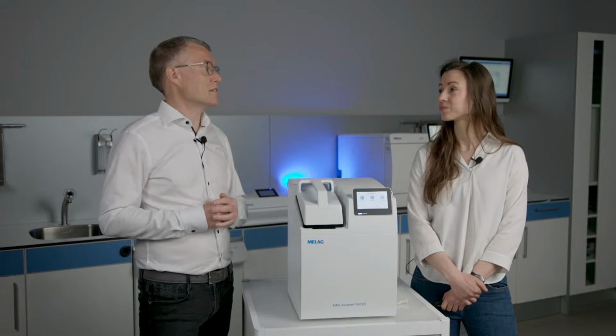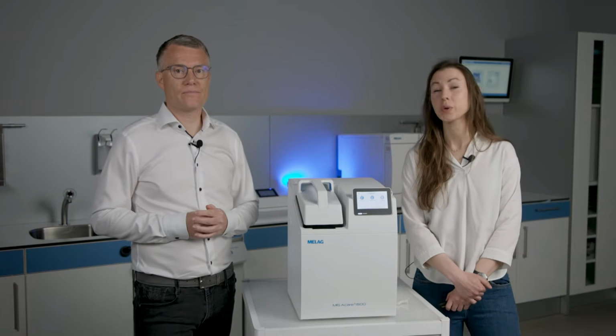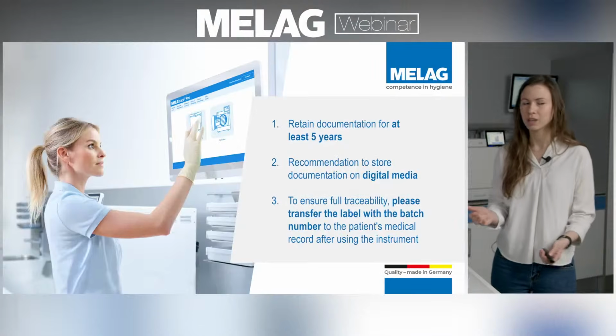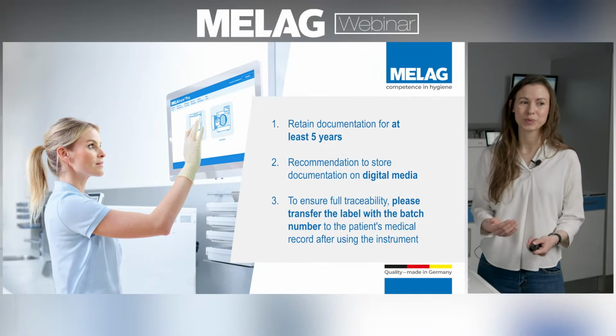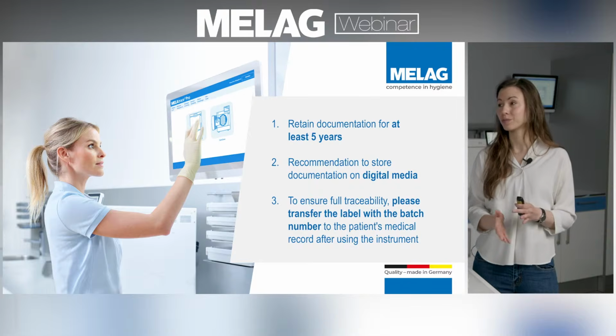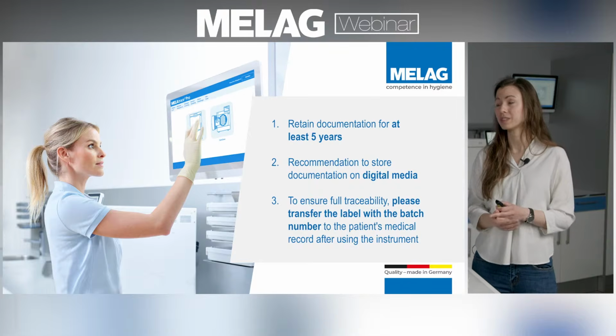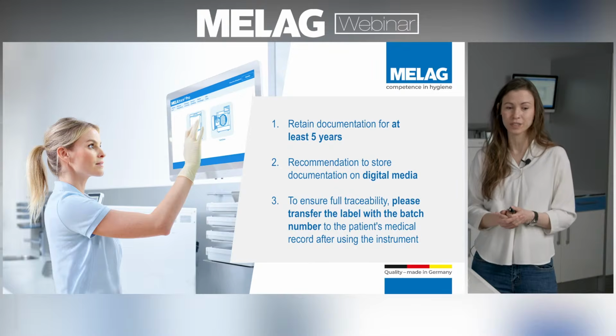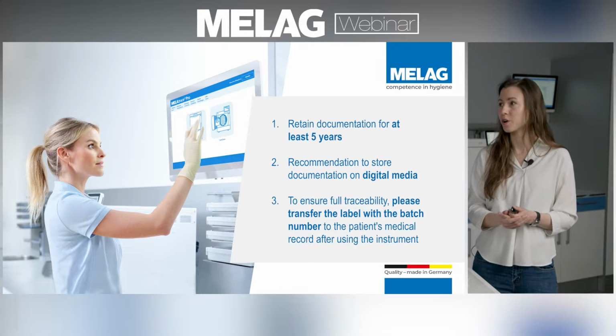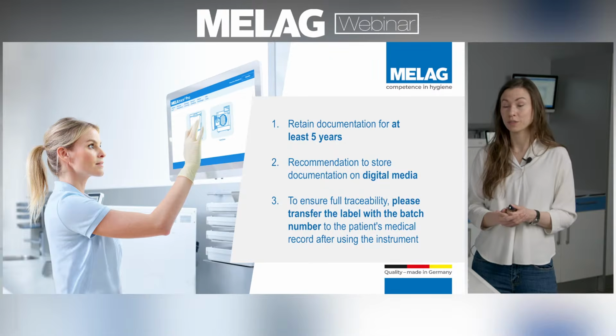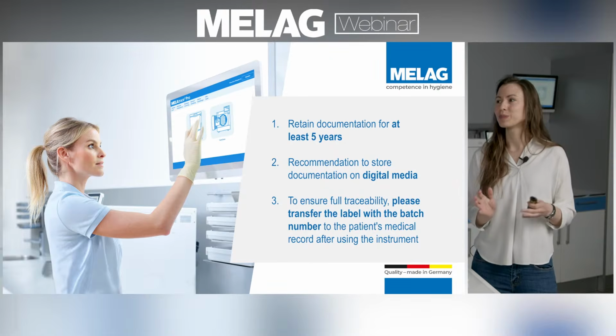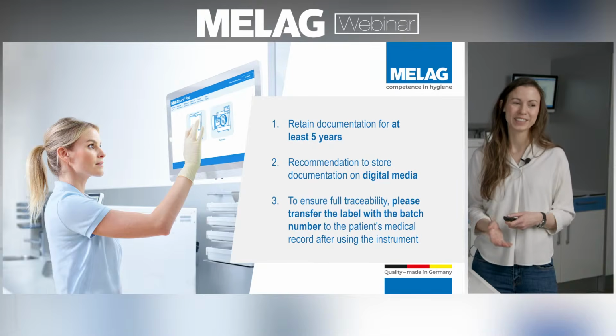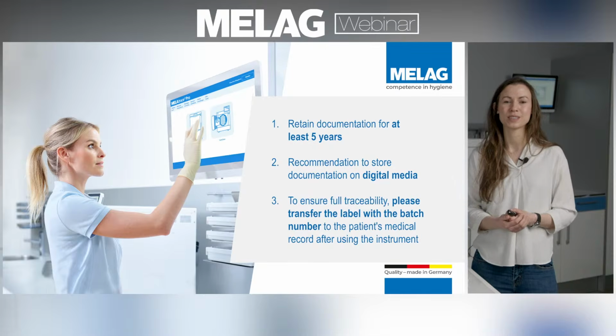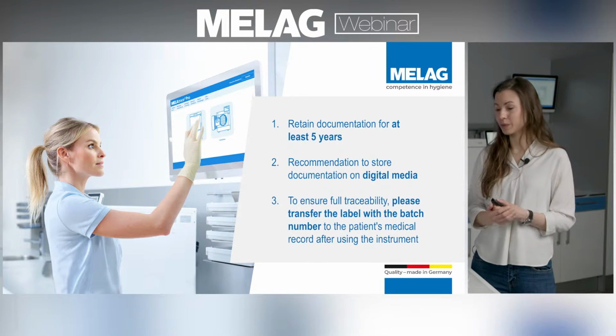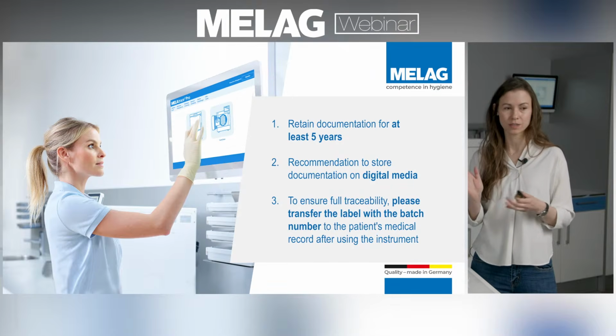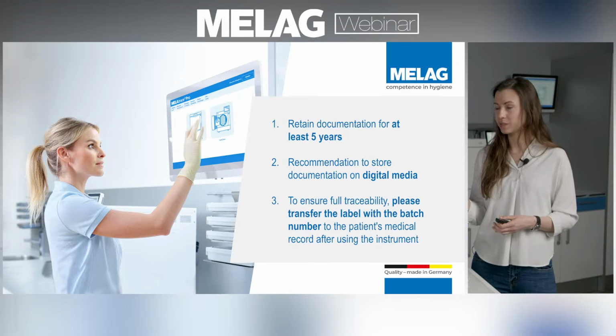is highly recommended. Yes, and in regards to how long do I actually have to keep the documents? If you do it manually, it's recommended to at least retain the documentation for 5 years. Some countries even have longer periods of time. For example, I think in Germany 10 years is common, in some cases even 30. And those documents will add up for the cycles, and therefore it's highly recommended to document this in digital form. As you mentioned, a lot of devices on the market offer this solution. Our devices do it too.